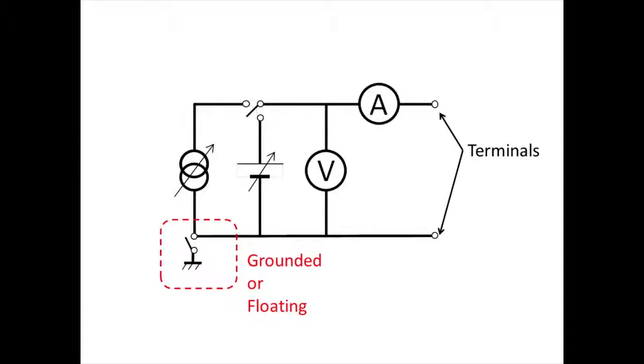SMU has two low terminal states. One is a grounded state, the other is a floating state. The low terminal state is set to floating state.